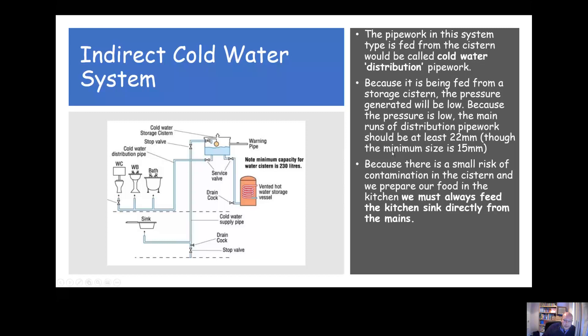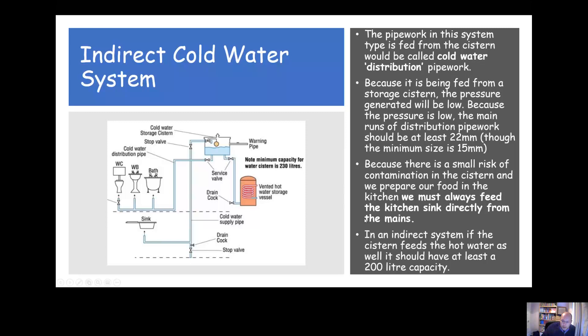There is always a risk of contamination in any system. As a result, you must always feed the kitchen sink from the mains, whether it's a direct or indirect cold water system. If an indirect system feeds both hot and cold, the storage cistern should have a minimum capacity of 200 litres — sometimes shown as 230 litres in the test.